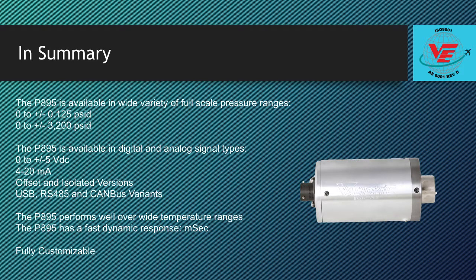In summary, the P895 is a compact, robust pressure transducer that is available in a wide variety of pressure ranges, from units with a full scale of just plus or minus 0.125 psid up to high pressure ranges of plus or minus 3,200 psid. The P895 is available in an extensive variety of standard analog as well as digital signal outputs and is digitally corrected for high performance over wide operating temperature ranges.